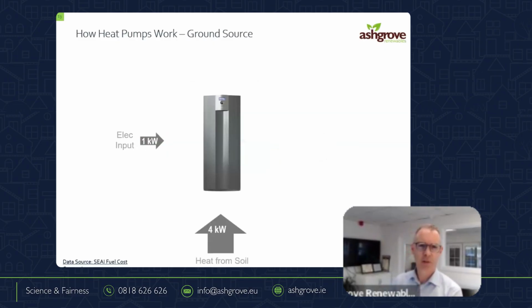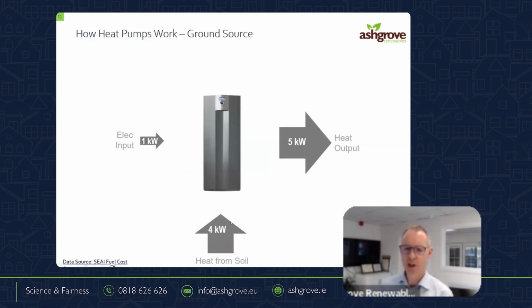So in the case of a ground source heat pump, we typically have slightly higher COPs. So I'm putting in 1, I'm getting 4 here, and I'm getting 5 out the far side. Now we can see that being up as far as 7 in some cases, right? If things are properly done and if the building is well designed, the pipework is correct, we've set it up properly, we've balanced it, and the person is operating it properly, we can see this up at 7.